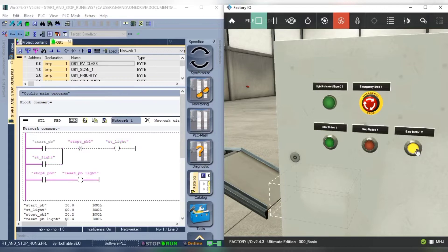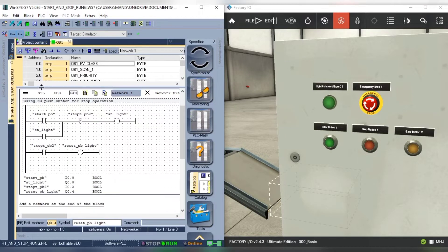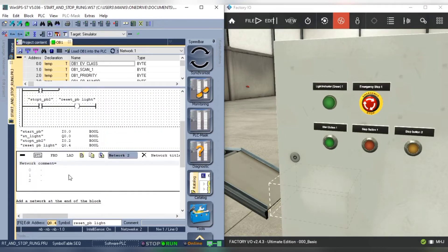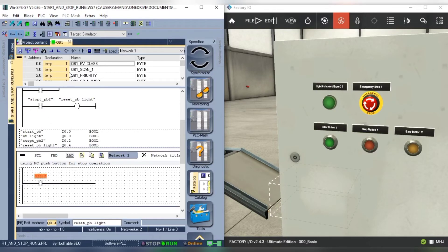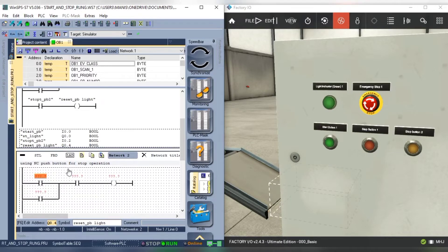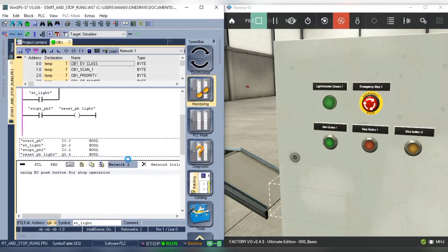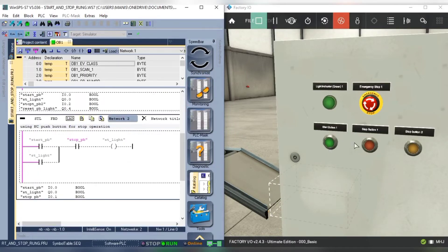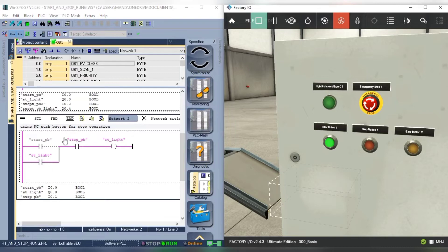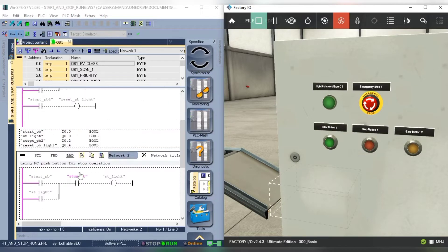When we press it we can see that the normally open contact gets closed, but in the above rung we have used a normally closed contact that opens, and the connection breaks so the output turns off. Now let's try creating the same using the stop push button. This time we need to change the contact form from normally closed to normally open contact. So let's modify it and test it. We can see that now we can turn the output on and off.